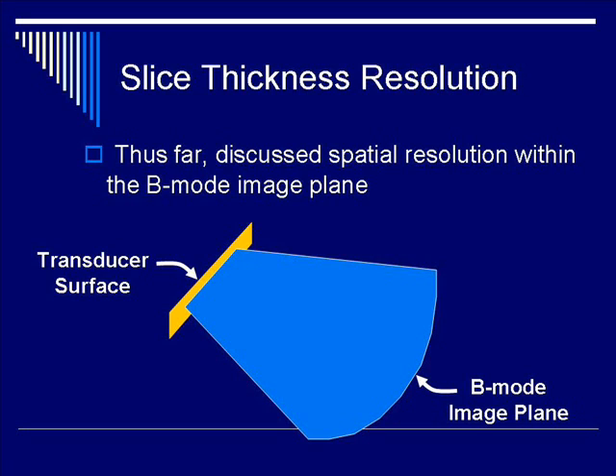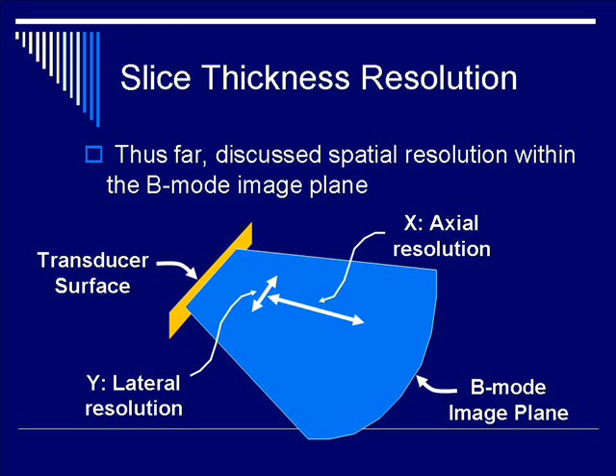So far, we've been discussing spatial resolution within the B-mode image plane, as shown in the cartoon below. The yellow bar denotes the transducer surface, which gives out the ultrasound beam, fanned out as indicated by the light blue signals. In the x-direction, denoted by the white line parallel to beam travel, is the x-direction describing axial resolution. Perpendicular to that is the y-direction, which is perpendicular to beam travel and is described by lateral resolution.